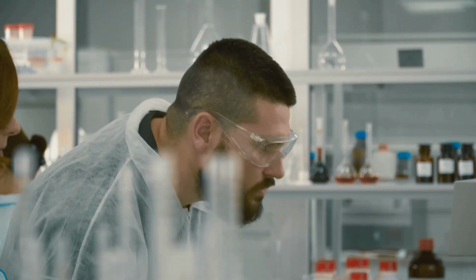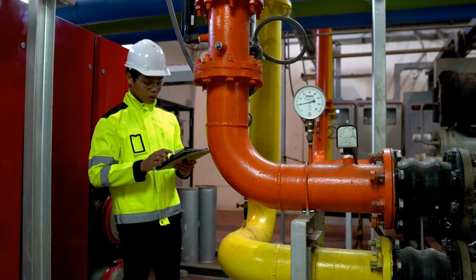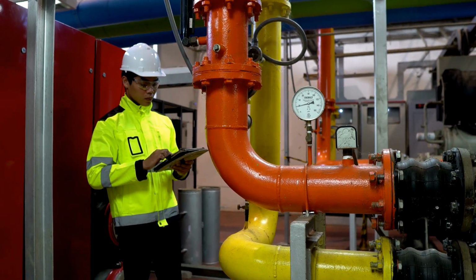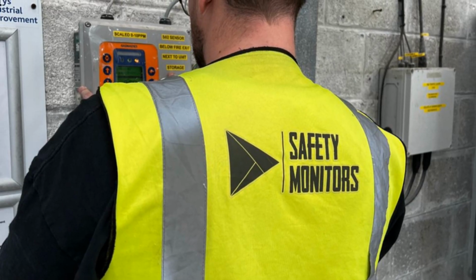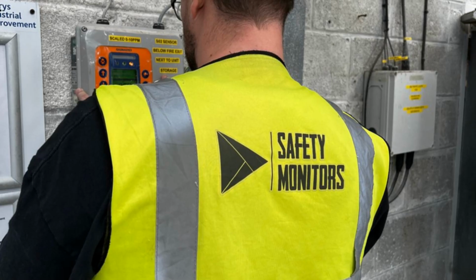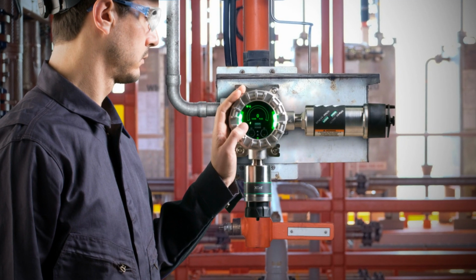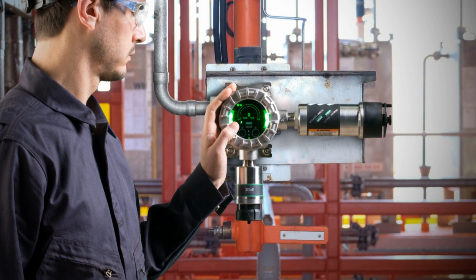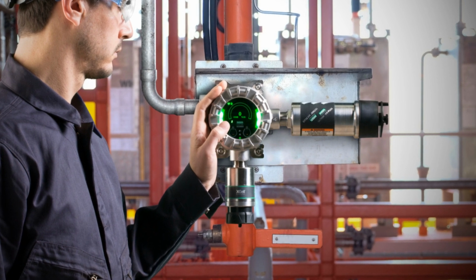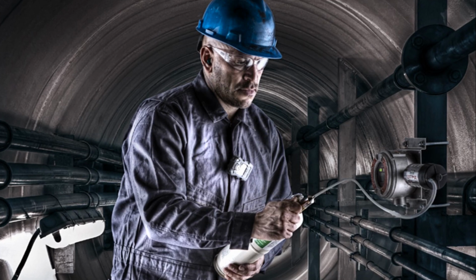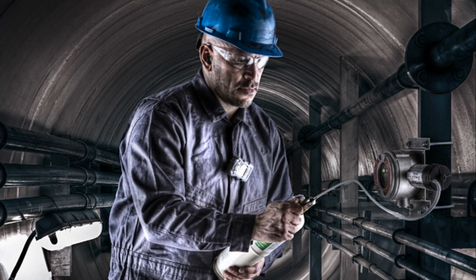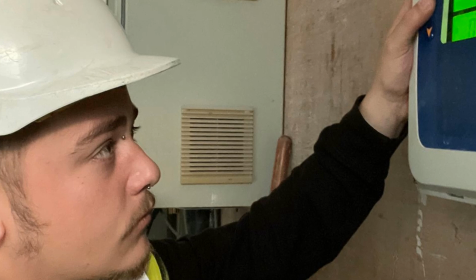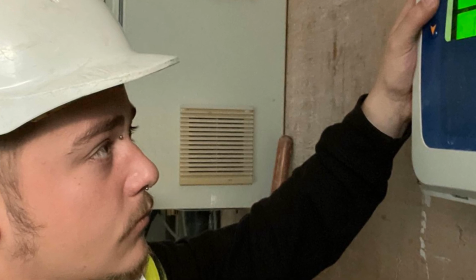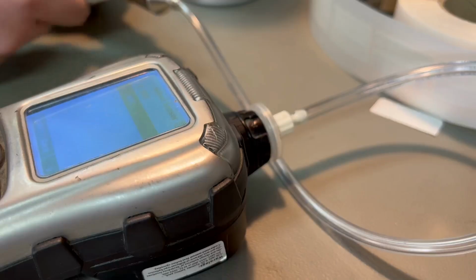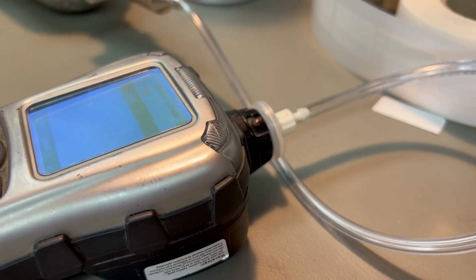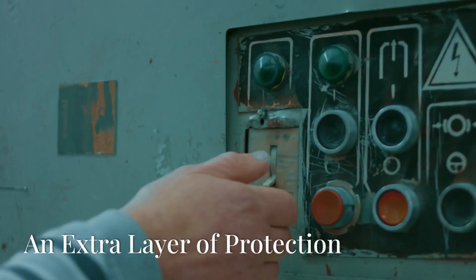Just like any other safety equipment, phosphine detectors need regular calibration and maintenance. This ensures they are functioning correctly and providing accurate readings. Calibration involves exposing the detector to a known concentration of phosphine gas to make sure it's providing accurate readings. Maintenance tasks include cleaning the detector and replacing any worn-out parts. Regular calibration and maintenance are essential for reliable phosphine detection.